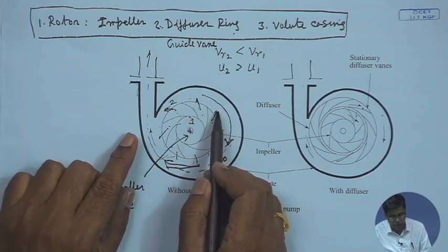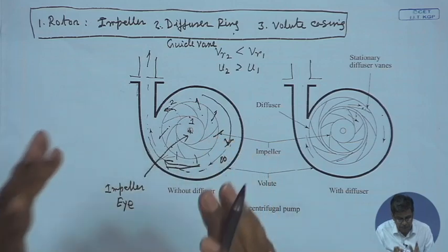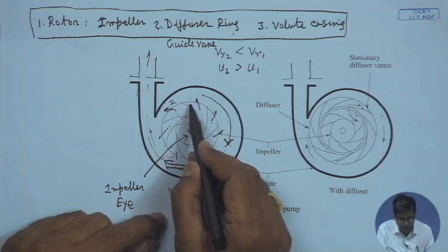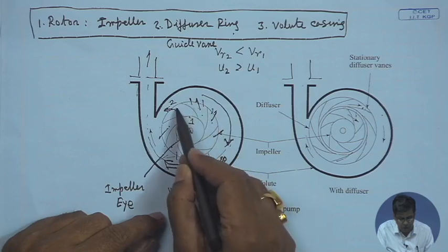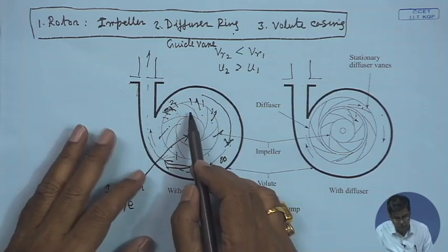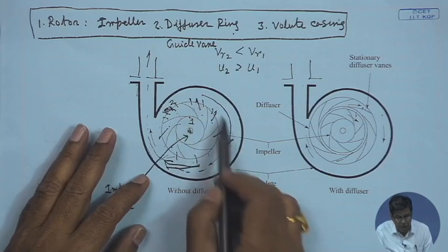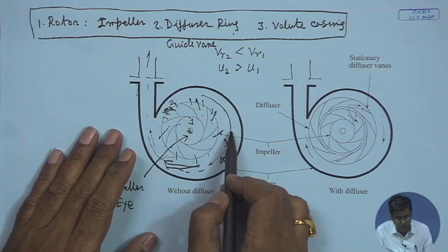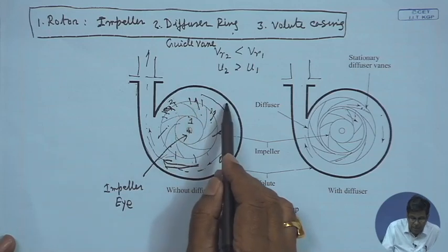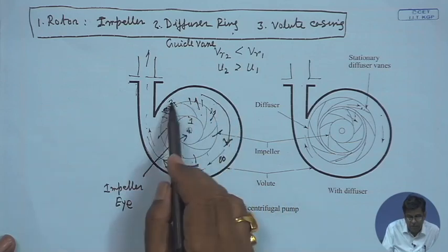If you neglect the viscous effect of the fluid, its angular momentum is conserved and the fluid executes a motion similar to free vortex motion with respect to its tangential velocity. At the same time, it is coming with a radial component of velocity from the impeller outlet, which under the ideal case is uniform. But there is non-uniformity for several factors — the viscous effect of the fluid in the passage plus the slip. So a radial flow is superimposed with a vortex flow close to that of free vortex flow, giving a spiral type of flow known as spiral vortex flow. The surface of the volute is designed to match the spiral vortex streamline for this spiral vortex flow.